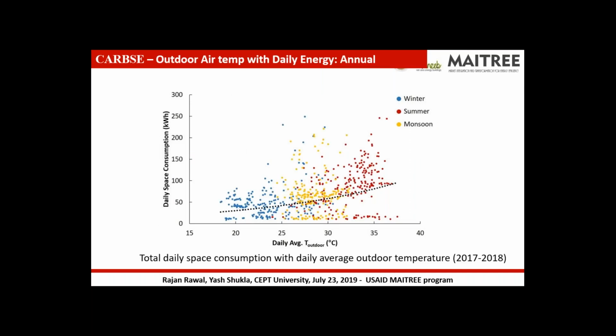Then we did a couple of analyses just to show the relationship of the outdoor temperature with the daily energy consumption, and you can see that the blue dots show the winter, the yellow shows the monsoon, and the red shows the summer energy consumption. You will see a moderate relationship between the outdoor temperature and the daily energy consumption. If this graph is steep, towards a 45 degree relationship, that means you actually have a very leaky building. A lot of impact is happening from the outdoor temperature on the building energy consumption. In an ideal scenario, you would have a flat line where the outdoor temperature has no impact. Maybe not an ideal scenario, but that's one way you can say there is no impact. But this shows a moderate relationship. So even after insulation, some heat gets in when the outdoor temperature is high.